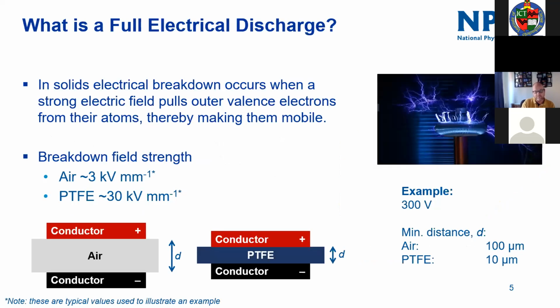But there are reasons why people use ceramics in high voltage work, and that's to a large extent dictated by electrical discharge within the systems. I'm sure we're all familiar with full electrical discharge that happens in air at around 3 kilovolts for every millimeter of spacing you have between conductors. If you put a dielectric between those, PTFE for instance, you'll push that up to about 30 kilovolts per millimeter. And when it does break down, there's obviously a lot of flash bangs and wallops going on.